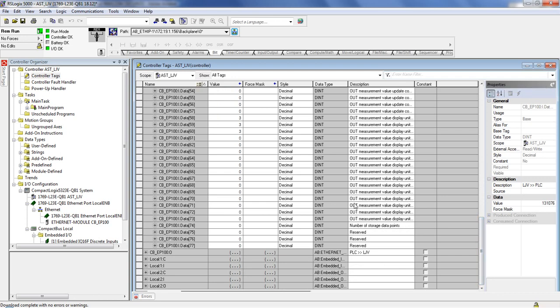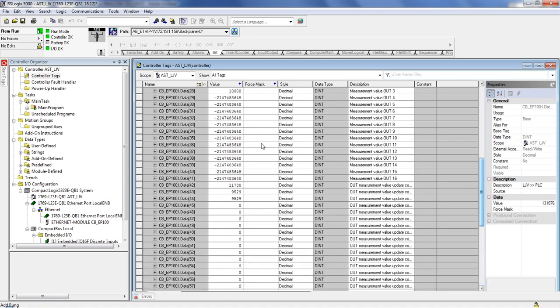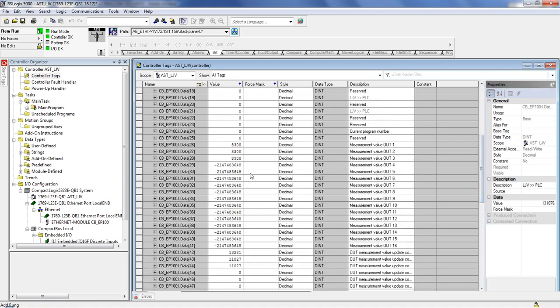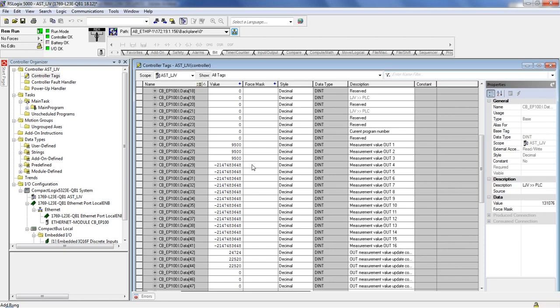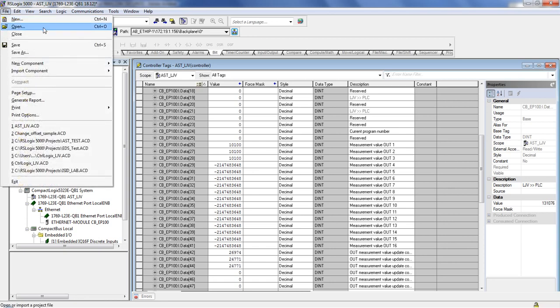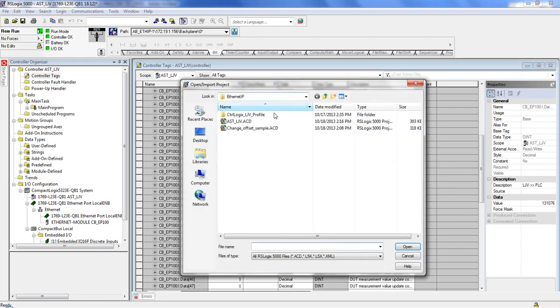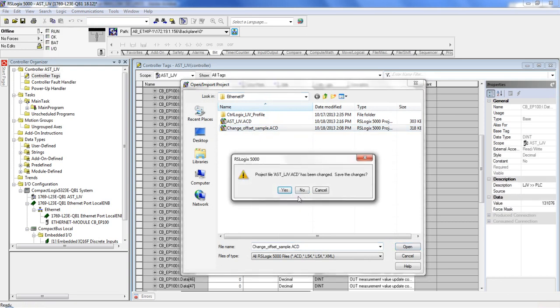The next step that I want to do is show some quick programming as far as changing some values on the unit. So what we see here is known as cyclic communication or implicit communication. So this is communication that's always going on in the background and just working on its own. To change a lot of the values or get maybe profile data from the LJV, you need to use something called explicit communication or messaging communication. This is going to be where we need to send the PLC or the LJV a certain command in order to get this information across. What I've done is I've already made a sample program for this. So this is going to be change offset sample. Let's go ahead and open this. I don't need to save anything there.